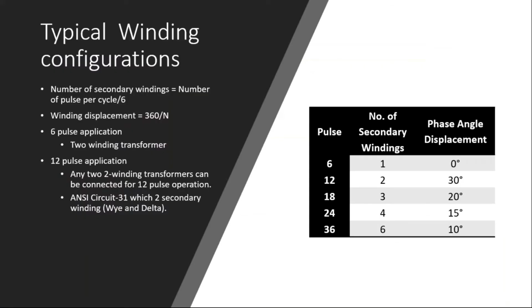So, talking a little bit about the design requirements. These transformers are normally applied in drive input, drive output, or variable speed applications, generator exciter, traction, and drive isolations. For all these applications, the design concept is different from normal power transformer design. For example, if you need n pulses in one cycle, the number of windings you need is n by 6. Say you want an 18 pulse requirement: n will give 3 secondary windings you need. And for a 12 pulse requirement, we need 2 secondary windings.